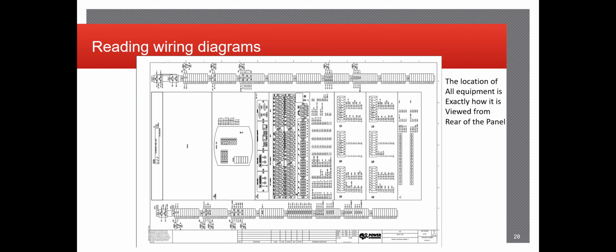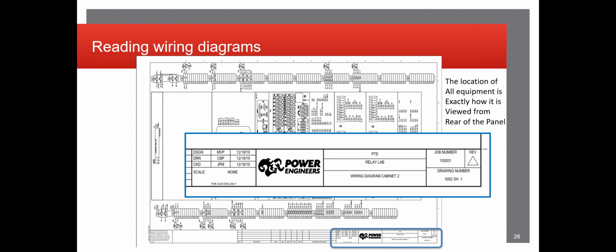Wiring diagrams look completely different than schematics. Wiring diagrams are usually what the electricians will go off of when they're putting the panel wiring together. They identify where the equipment is going to be specifically in the panel, and identify all the naming conventions for all the terminal blocks, relays, test switches, lockouts, etc. And it should be a fairly good physical representation of what the panel should look like. Again, title blocks identifying the drawing, which cabinet and job numbers, etc.